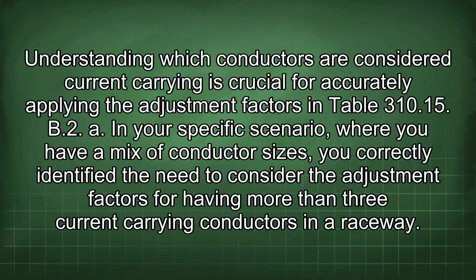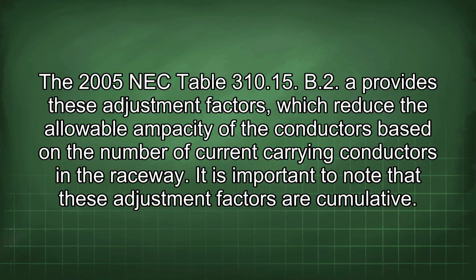In your specific scenario, where you have a mix of conductor sizes, you correctly identified the need to consider the adjustment factors for having more than 3 current carrying conductors in a raceway. The 2005 NEC Table 310.15 B2 provides these adjustment factors, which reduce the allowable ampacity of the conductors based on the number of current carrying conductors in the raceway. It is important to note that these adjustment factors are cumulative.